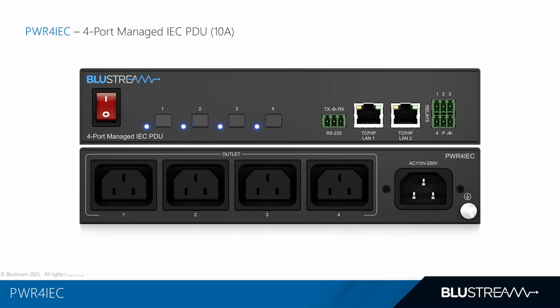Let's start with the PWR4 IEC, our compact managed PDU designed for smaller AV and data racks. It delivers power where you need it without wasting rack space. Electrically, it uses a C14 inlet supporting 110 to 250 volts up to 10 amps. Now, this is feeding 4 IEC C13 outlets, which is, of course, ideal for higher draw AV devices like network switches, video processors, audio gear, and control systems. The half-rack 1U form factor keeps layouts tidy, and we include rack mount wings so you can drop it straight into a build.